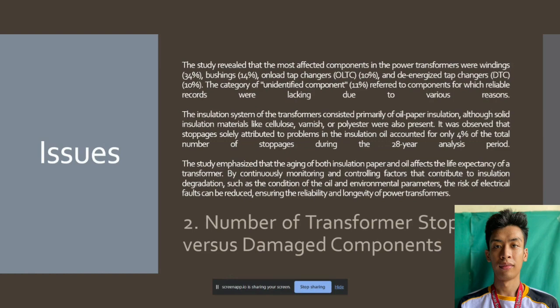The insulation system of the transformers consisted primarily of oil paper insulation, although solid insulation materials like cellulose, varnish, or polyester were also present. It was observed that stoppages solely attributed to problems in the insulation oil accounted for only 4% of the total number of stoppages during the 28-year analysis period. The study emphasized that the aging of both insulation paper and oil affects the life expectancy of a transformer. By continuously monitoring and controlling factors that contribute to insulation degradation, such as the condition of the oil and environmental parameters, the risk of electrical faults can be reduced, ensuring the reliability and longevity of our transformers.